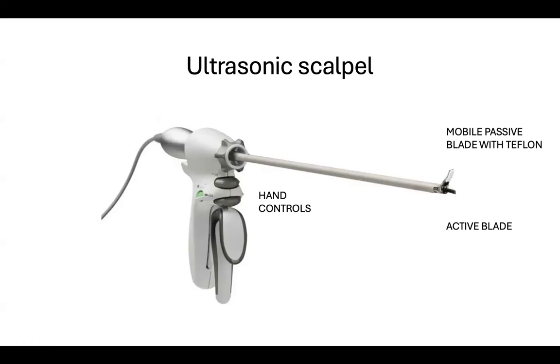So a lot of people say this is costly, we are not able to use much. The only problem is that you're not keeping enough tissue between the blades, or even if you are keeping tissue, you are crushing it, or you are continuing to activate the instrument even after the tissue is cut or coagulated. So the number of cases you can preserve this Teflon for, that long this instrument will last. You'll be amazed to know, even these Ethicon people are amazed, because some of my probes last for 20 to 25 cases. That is not about any great thing, it's just because of how much you preserve this Teflon coating. That is the key about this instrument.